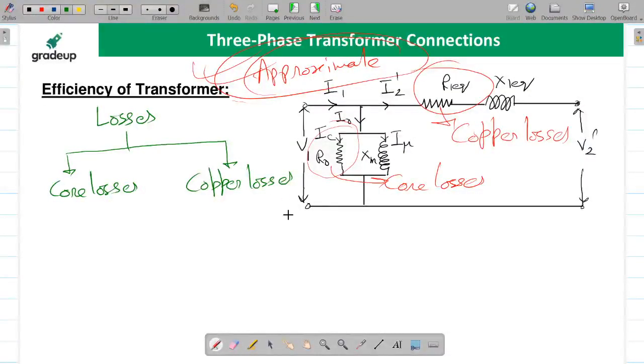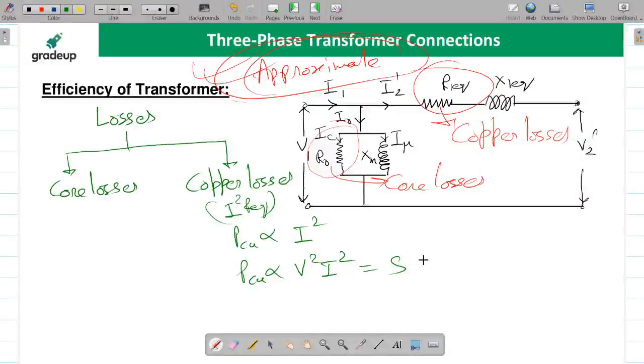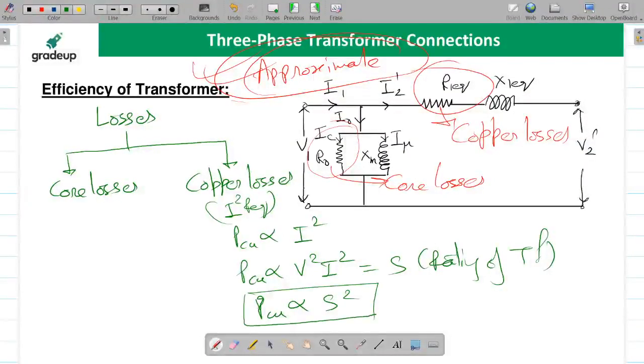Now the copper losses are nothing but your I square R equivalent losses. So you can say the copper losses are directly proportional to the square of the current, because R is going to be constant once you design the transformer. Or you can multiply it with the voltage square, so this is nothing but the rating of the transformer. So the copper losses are directly proportional to the square of the rating of the transformer. This is important, just note this down.